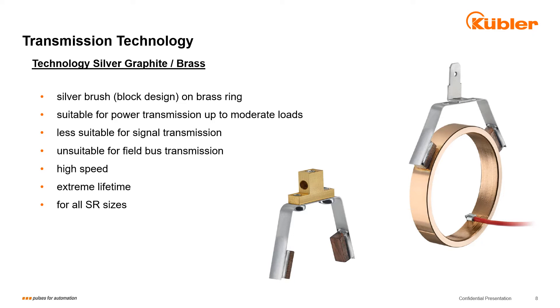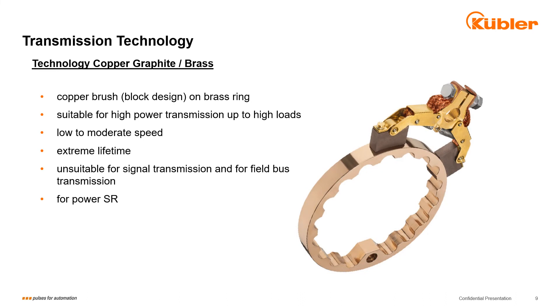The simplest combination is a spring-loaded silver graphite block that runs on a brass ring. This combination is often used for power transmission and sometimes for insensitive analog signals such as 4–20 mA or 0–10 V. It is perfectly suitable to activate electric valves or similar actuators and serves as auxiliary power supply for motor controllers. For high current up to 150 A and voltage up to 1000 V, the ring is massive brass and the transmission blocks are made of a copper graphite compound. All silver or copper-based combinations described so far are designed for robust use and long service life.